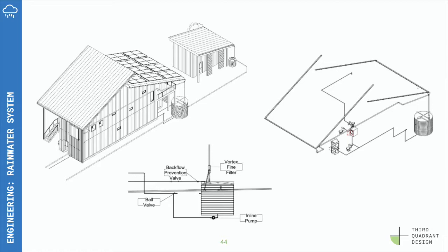In a world affected by climate change, water quality and availability can quickly deteriorate. To improve resiliency and off-grid capabilities, a rainwater harvesting system is implemented. Rainwater is directed from the roof to a 10,000-liter tank capable of supplying non-potable needs, that is, toilets, washers and dryers, and irrigation for the vertical garden. The tank is sized for a month's supply without rain.